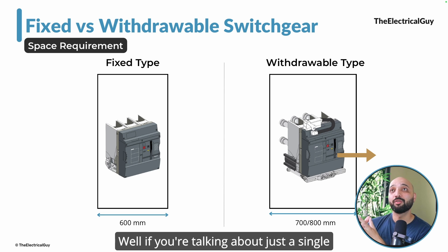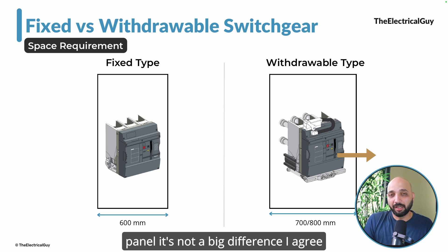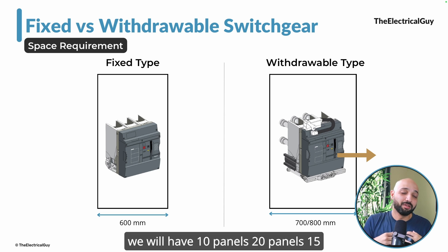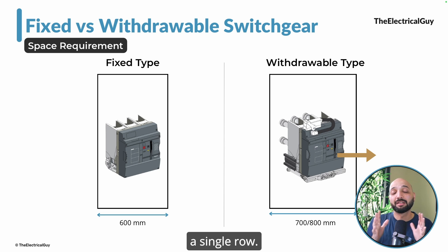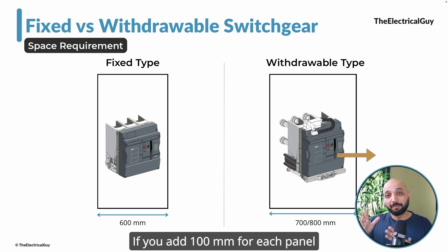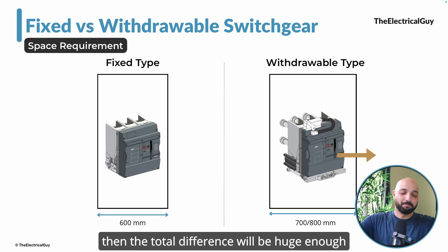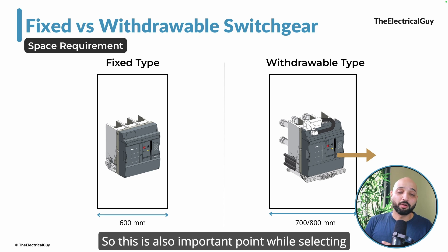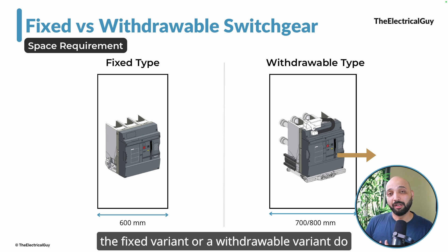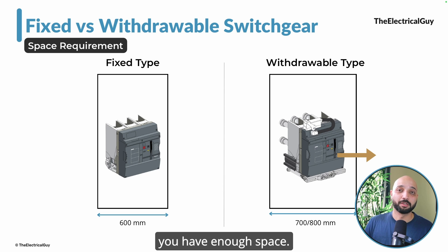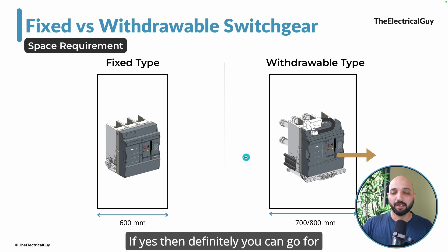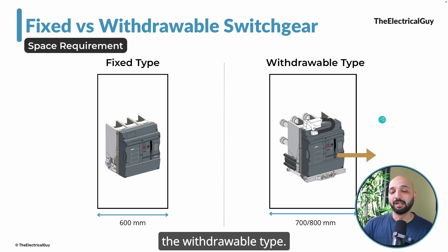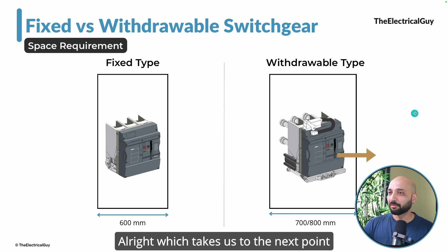For a single panel the difference may not be huge, but in a substation with 10, 15, or 20 panels in a row, adding 100 mm per panel means the total space difference becomes significant. Space availability is therefore an important consideration — if you have enough space, you can go for the withdrawable type.